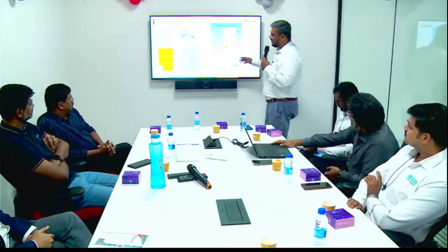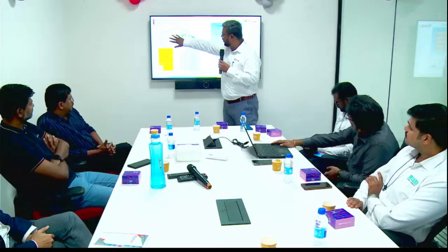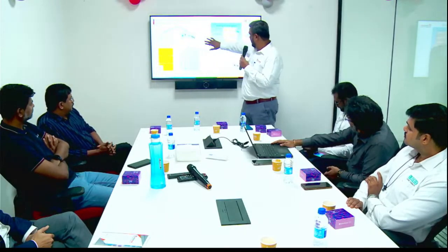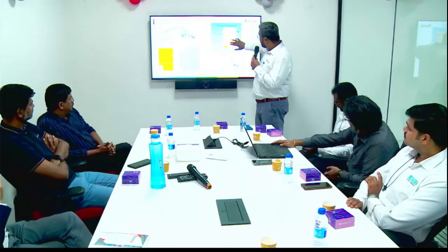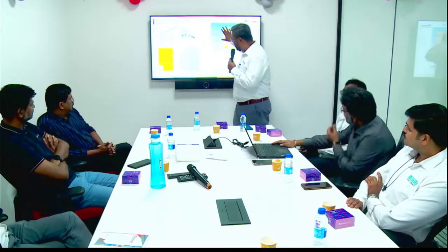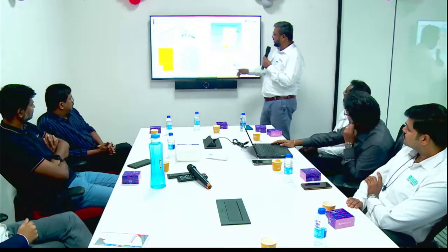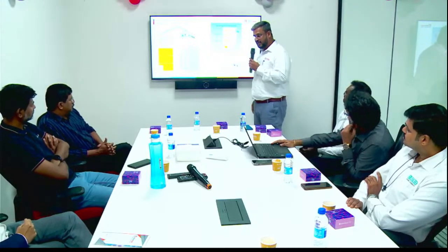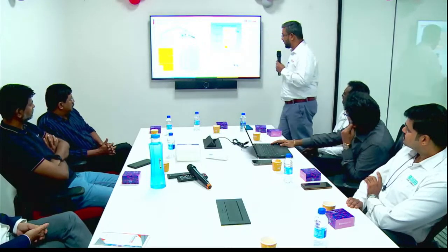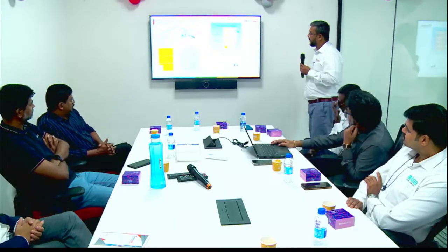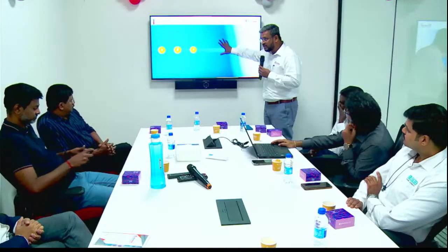This is the horizontal cabling. So, work area. This is the data center. This is the horizontal cabling, and this is the intra-building cabling, within the building. Inter-building cabling is building to building. This is for the ISP. The ISP we usually have to terminate in the front office facility only. We should not bring the ISP into the data center. This is the recommendation. I'm talking about the recommended standards only.